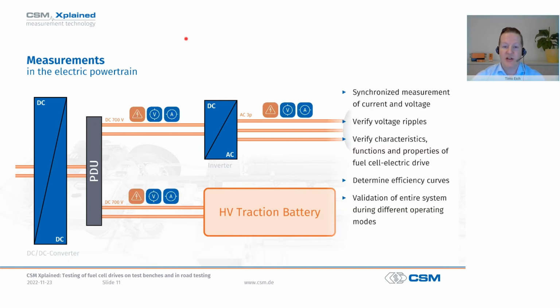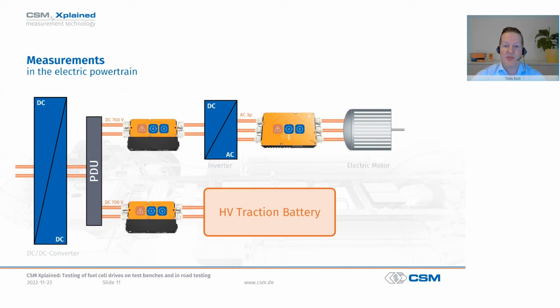Our developers are now interested in the energy flows between all of the components of the electric powertrain, and so they want to measure voltage and current at various points between the components. For example, between the PDU and the inverter, between the PDU and the battery, and between the inverter and the electric motor. And now we can investigate, amongst other things, voltage ripples in the DC circuit. We can determine efficiencies, for example, the efficiency of the inverter, and we can examine the entire system in various operating states. And for this purpose, we again take our high voltage breakout modules and insert them directly into the high voltage cables between the individual components in order to record voltage and current completely synchronously and high voltage safely.